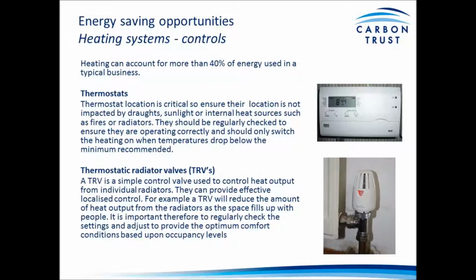And we'll start by looking at heating systems. As I say, that's perhaps the most common of the HVAC systems that we come across. And typically, heating systems can account for more than 40% of energy use in a business, so it's a very valid place to start. In terms of simple control for heating systems, particularly gas-fired wet systems, the most common ones we see, thermostats and standard timers are one of the key aspects of controlling a heating system.